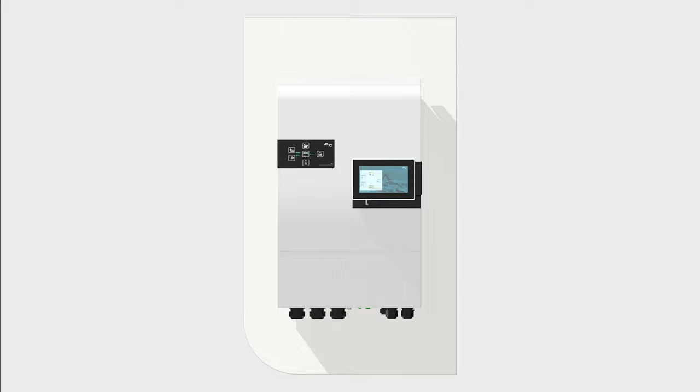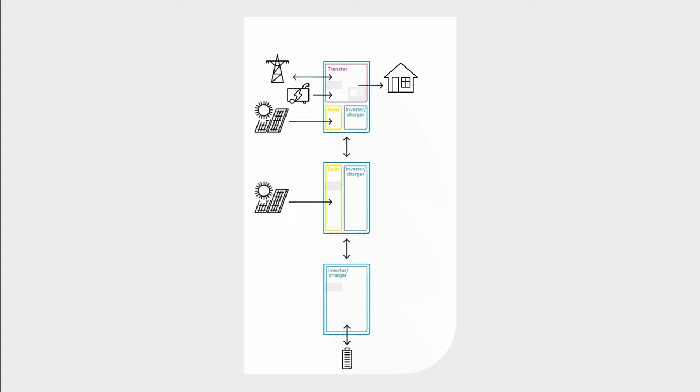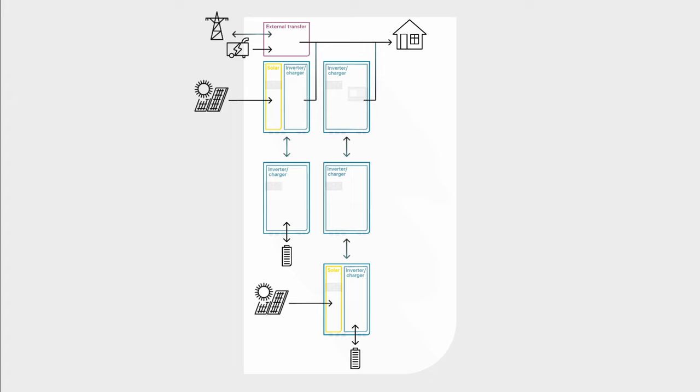Multiple units can be combined in parallel with a unique transfer and a common battery. And for the very first time, it is also possible to combine multi-unit and multi-battery systems using an external transfer, allowing even different battery technologies and increasing the versatility with centralized management.